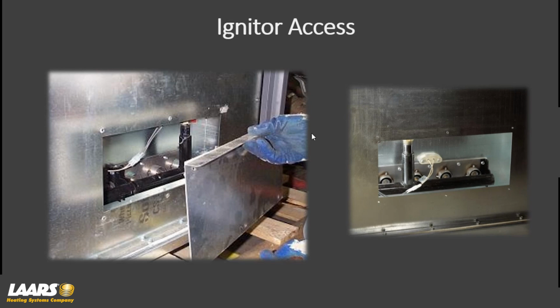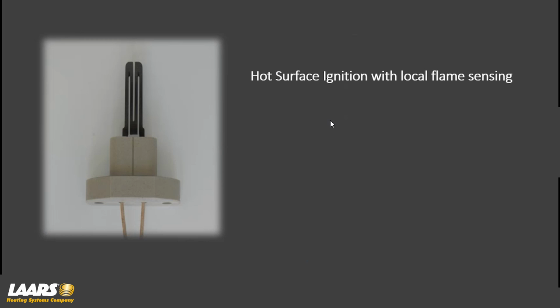Next, I'll talk about the Ignitor Access, and I mentioned to you about the access panel. So we have the Ignitor Access right here. That's held into position with 2 screws. There is a gasket in behind the igniter. Now, hot surface igniter or ignition, the one we use, these are made by Norton. Some manufacturers will use an igniter and a flame rod. We do not. Our igniter is both used to ignite the product.